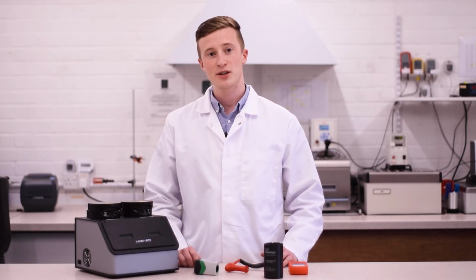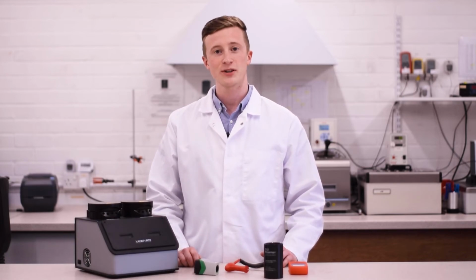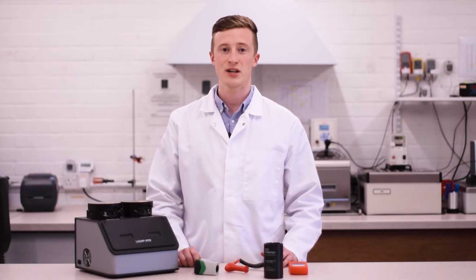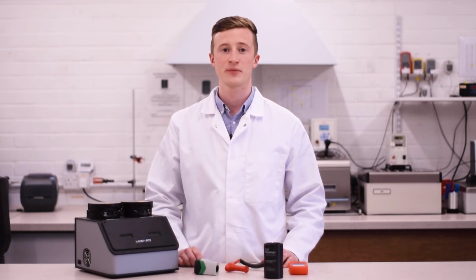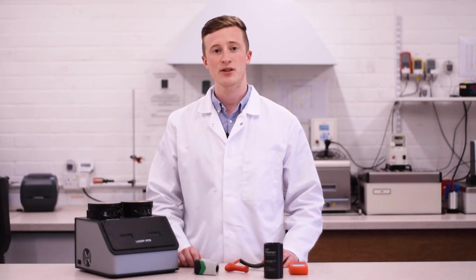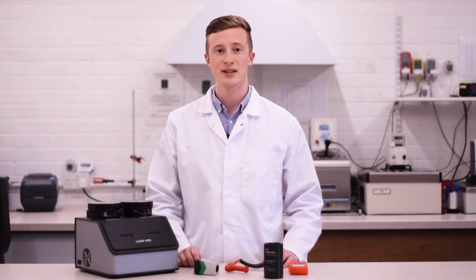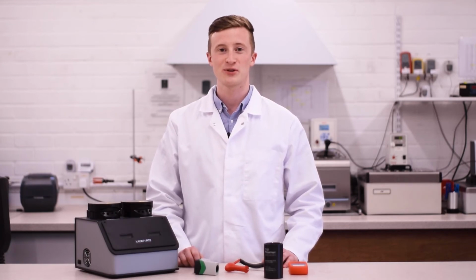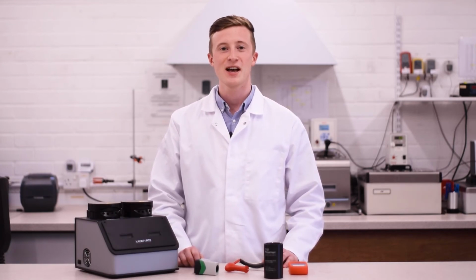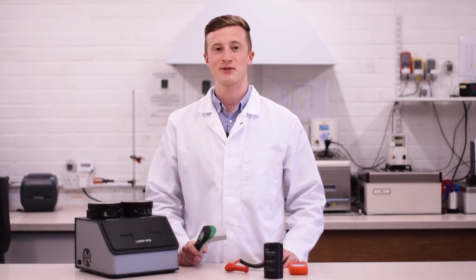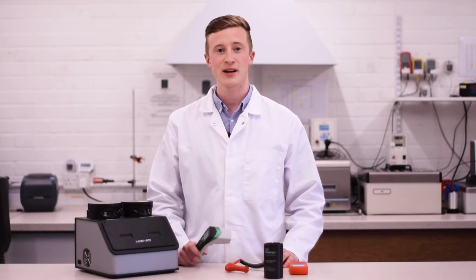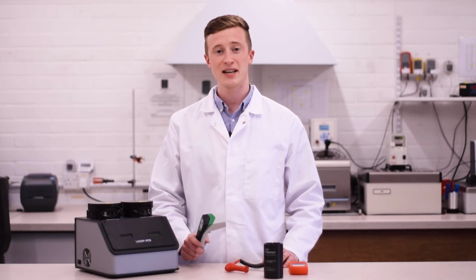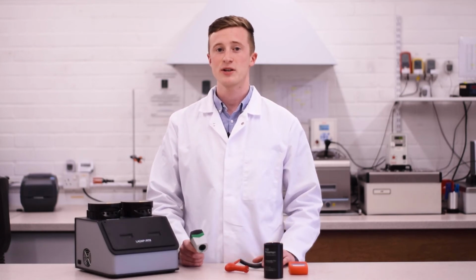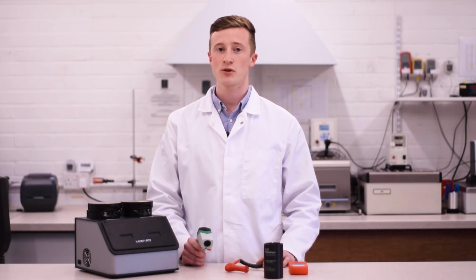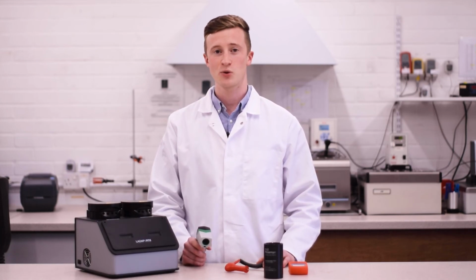So this process using the LaserPort 8 allows a much faster checking process, as well as verification at 2 different temperature points. Typically, LaserPort calibrators are also calibrated to UKAS standard. This is a big thumbs up with auditors, as it increases the traceability and improves the standard of your testing regime. Remember to carry out this process regularly, ideally daily or each shift, and document your verification results. Also remember to have this information ready for your auditors to check if required.